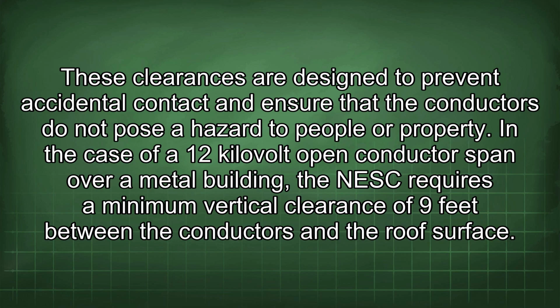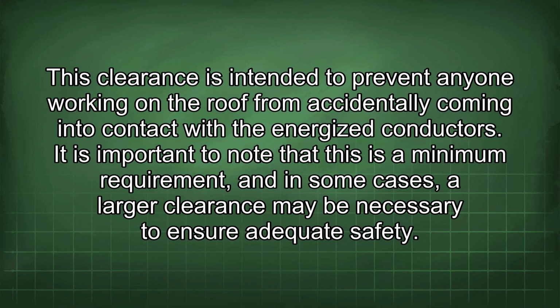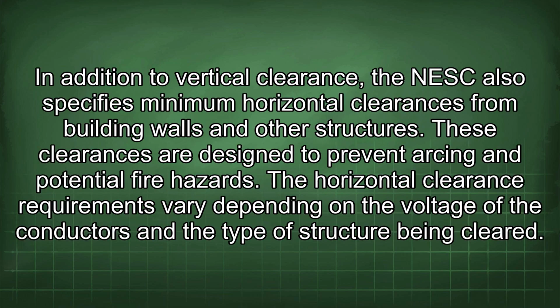These clearances are designed to prevent accidental contact and ensure that the conductors do not pose a hazard to people or property. In the case of a 12 kV open conductor span over a metal building, the NESC requires a minimum vertical clearance of 9 feet between the conductors and the roof surface. This clearance is intended to prevent anyone working on the roof from accidentally coming into contact with the energized conductors. It is important to note that this is a minimum requirement, and in some cases, a larger clearance may be necessary to ensure adequate safety. In addition to vertical clearance, the NESC also specifies minimum horizontal clearances from building walls and other structures. These clearances are designed to prevent arcing and potential fire hazards. The horizontal clearance requirements vary depending on the voltage of the conductors and the type of structure being cleared.